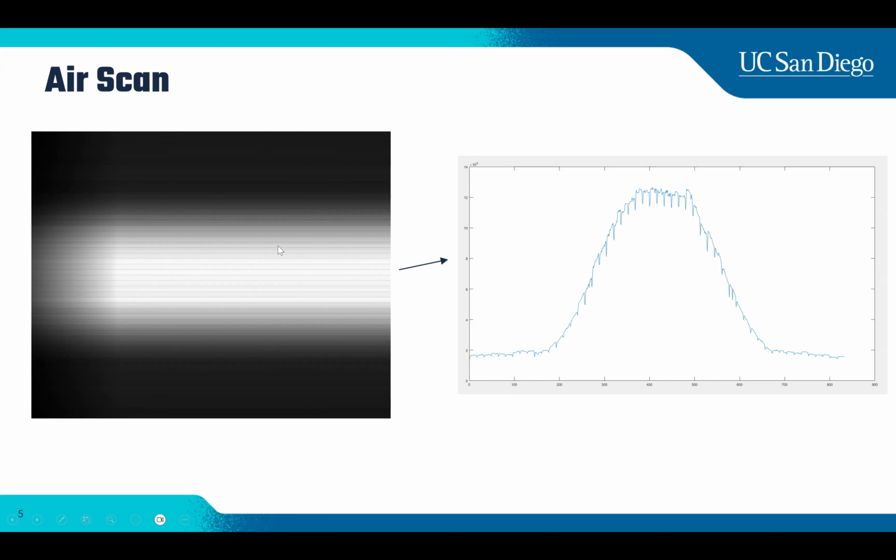So you can see there's some strips over here. If you plot one slice of the sinogram, it looks like this. You can see all those dents. These are the locations of your grids. So all we want to do is try to remove all those.